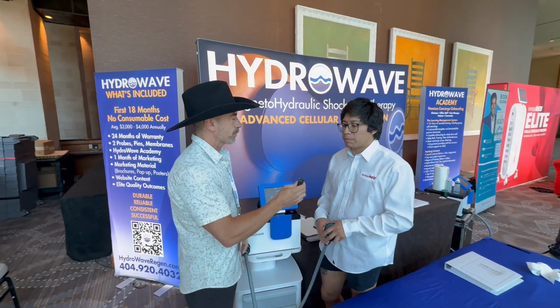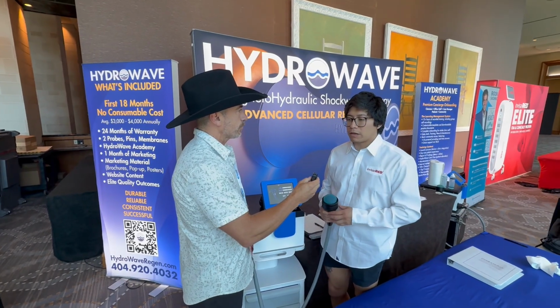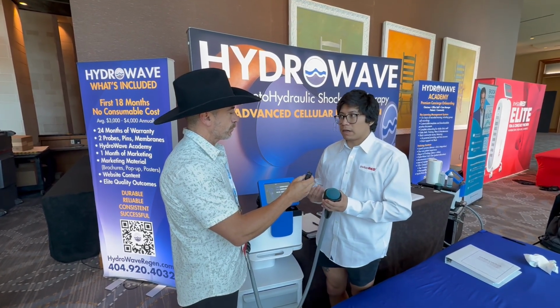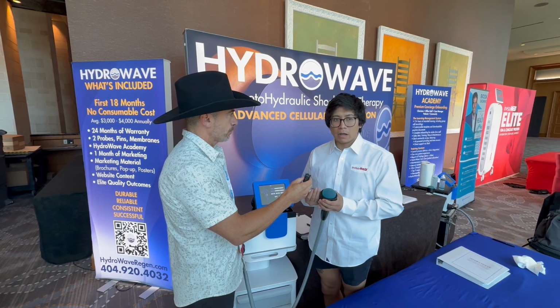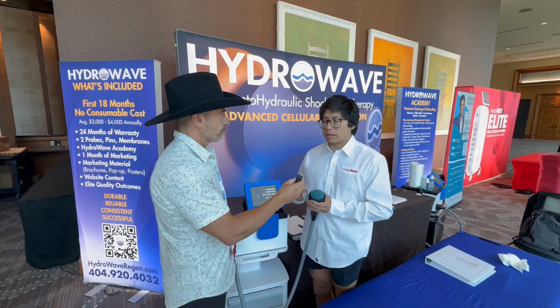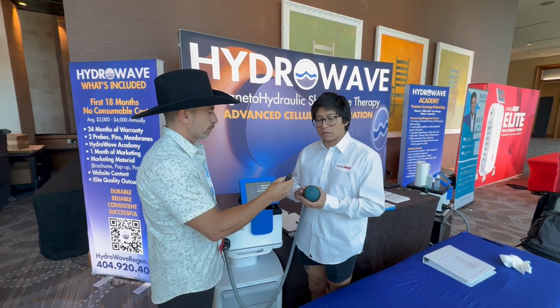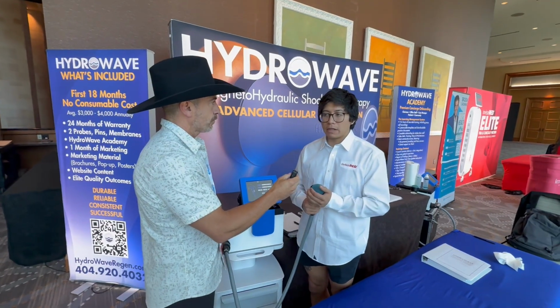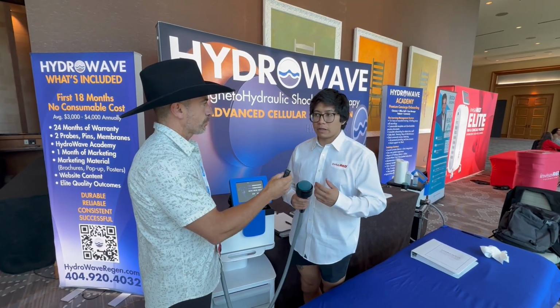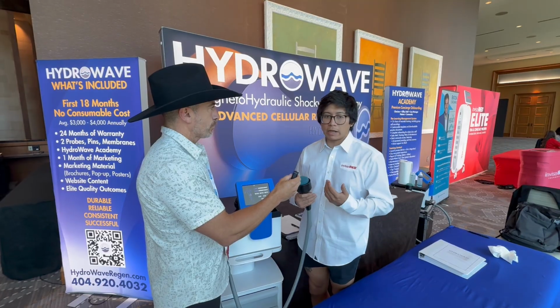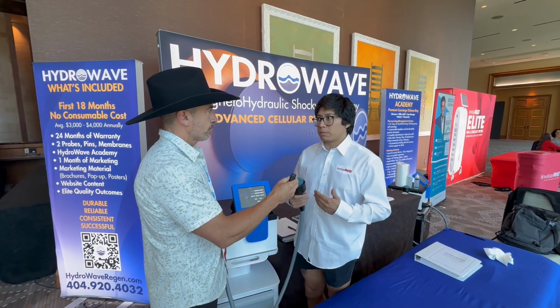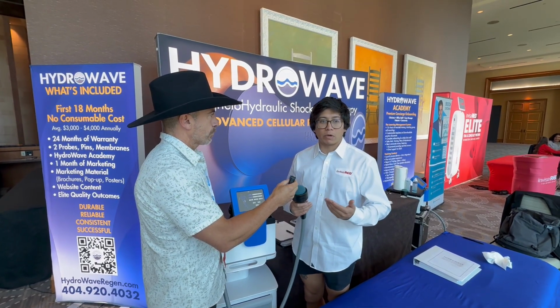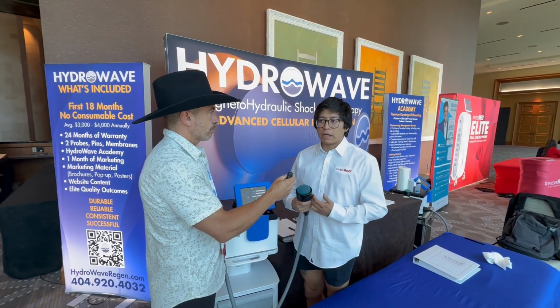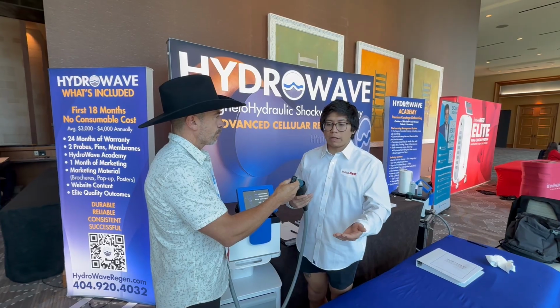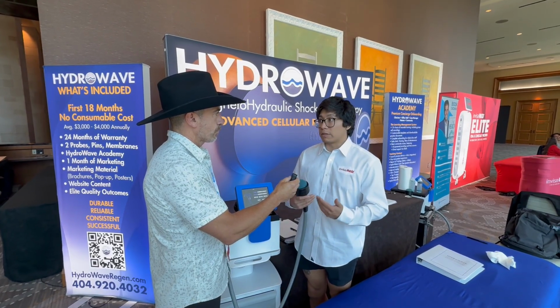Yes, so the biggest thing with the other devices is that the actual spark happens inside the water itself at the top of the head, where it's oxidizing the actual metal material that's causing the spark. So in each one, there is a spark inside that has water in there, so it's going to oxidize the material through electrolysis, which then leads to the device not making a proper or consistent spark or shock. So then you're going to get inconsistent shocks with the patient, and that could also harm the patient or not even provide any therapeutic benefit to them. Got it.